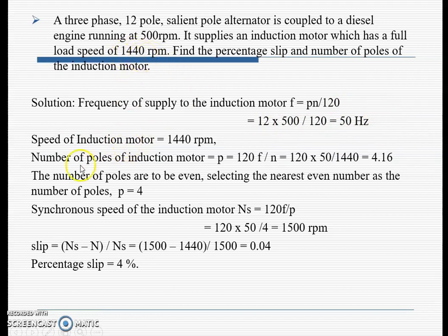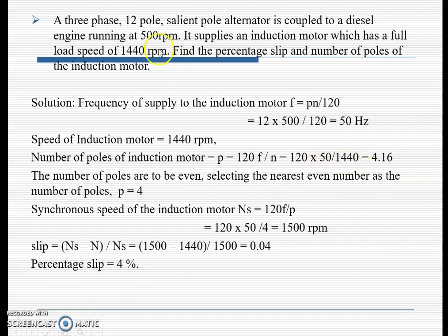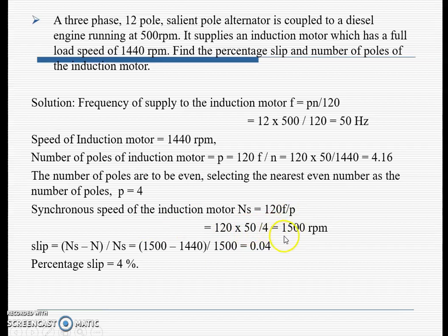The speed of the induction motor is given as 1440 rpm. The 12 poles belong to the diesel engine running at 500 rpm. For the induction motor, the number of poles is P = 120f / n = 120 × 50 / 1440 ≈ 4.17. Since the number of poles must always be even, rounding off gives P = 4. The synchronous speed for the induction motor is then n_s = 120 × 50 / 4 = 1500 rpm.